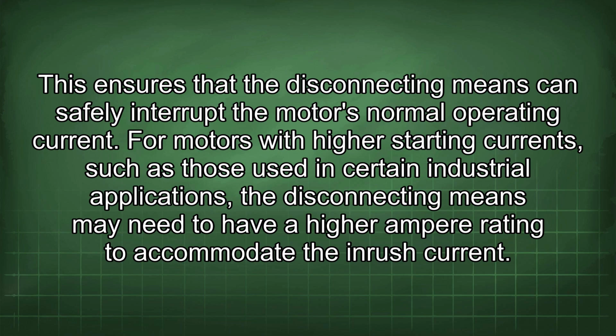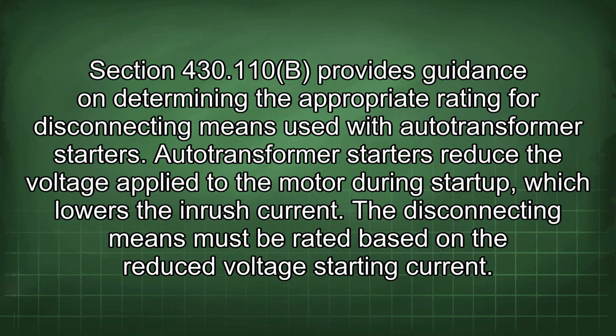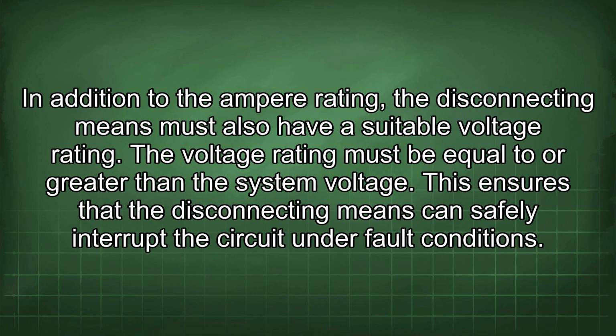For motors with higher starting currents, such as those used in certain industrial applications, the disconnecting means may need to have a higher ampere rating to accommodate the inrush current. Section 430.110b provides guidance on determining the appropriate rating for disconnecting means used with autotransformer starters. Autotransformer starters reduce the voltage applied to the motor during startup, which lowers the inrush current. The disconnecting means must be rated based on the reduced voltage starting current. In addition to the ampere rating, the disconnecting means must also have a suitable voltage rating. The voltage rating must be equal to or greater than the system voltage. This ensures that the disconnecting means can safely interrupt the circuit under fault conditions.